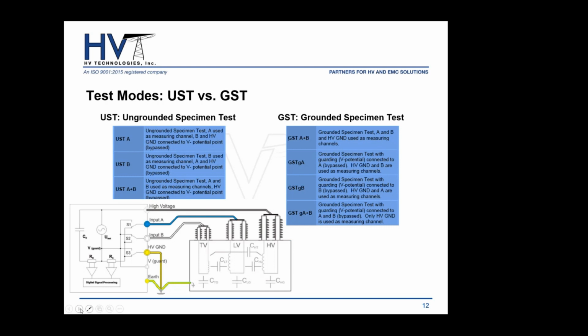So basically, we have 2 test modes when we do these types of measurements. We have one, the UST or ungrounded specimen test. We also have the GST or the grounded specimen test. So basically, any capacitance that is being measured from a winding, for example, to ground, or from a cable core to ground, you will test with a GST, grounded specimen test. You will select that mode on the instrument, and you will do your connections considering that you're doing a grounded test. For any interwinding, like in this case, in this figure, we have 3 winding transformers.